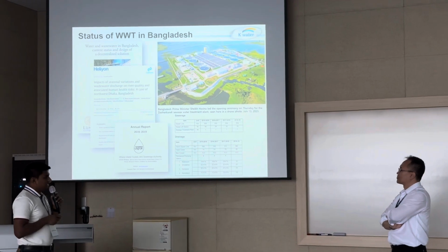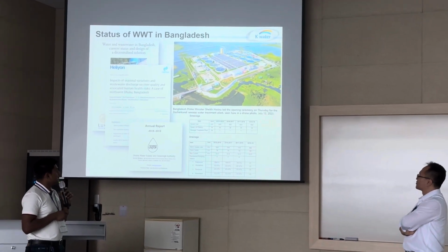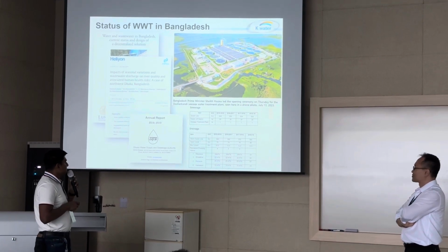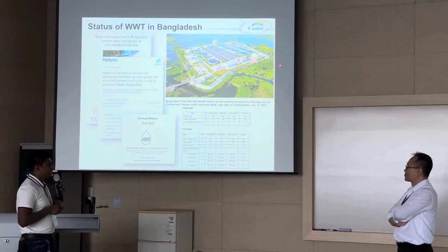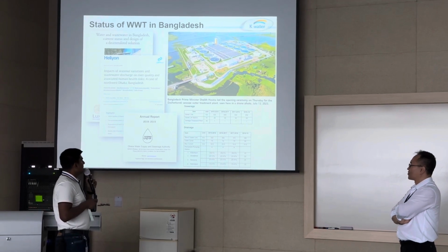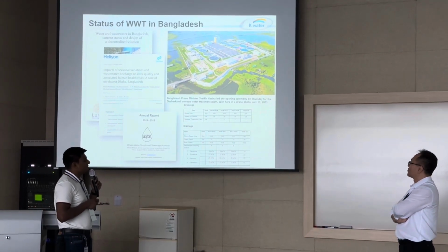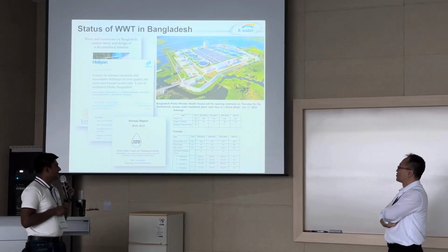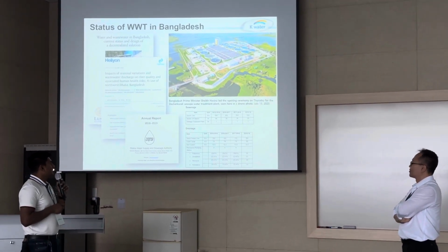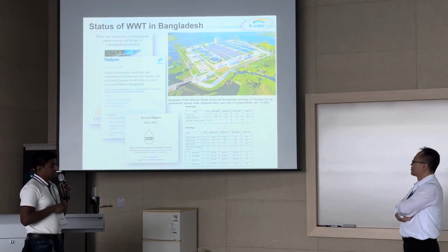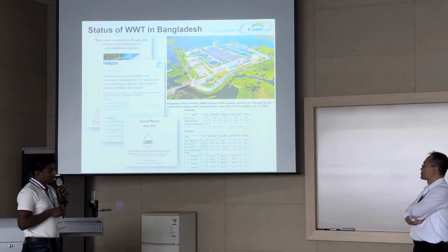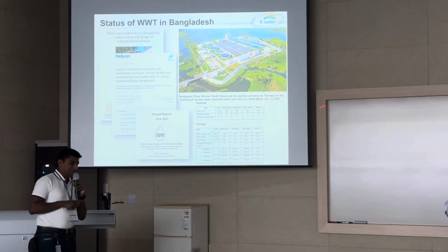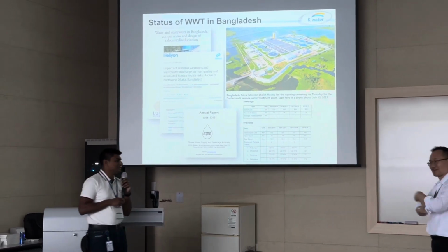We have a very updated, world-class laboratory, and the water we use for flue gas purification is actually treated water, and the effluent quality is very good. The ammonia in the influent is around 12 to 20 milligrams per liter, but in the effluent the ammonia is below 0.25 milligrams per liter. Yeah. So thank you. I took so much time. Thank you for giving me the floor.